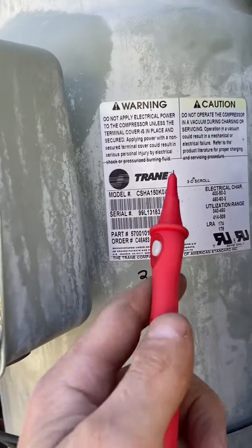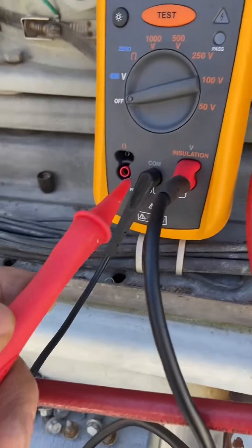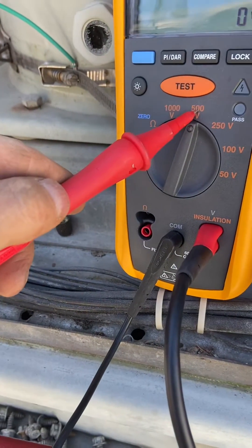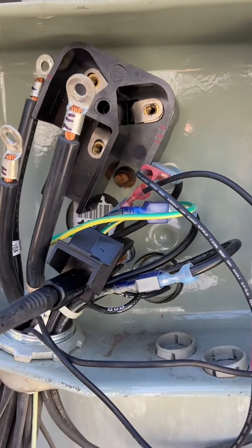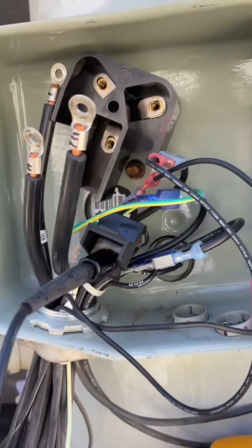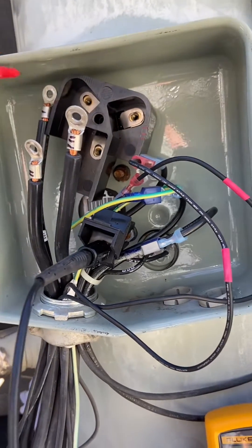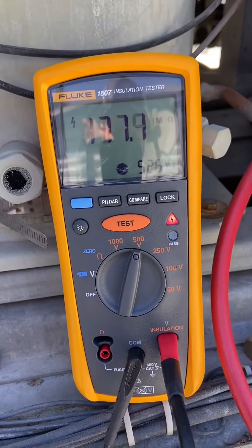I'm going to show you how to meg-test this three-phase compressor. It's in the Trane IntelliPak — it's easier just to voice over since those units run so loud. Got my Fluke. This compressor is 460 volts, so you put the meter up to 500 volts when you're testing. You can do 1000V, but based on the motor voltage you want to test at the range it's running at. This meter has the test button on the actual probe; if you don't have a Fluke it'll just be right on the face.